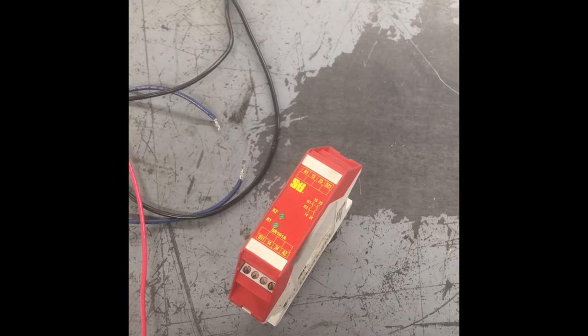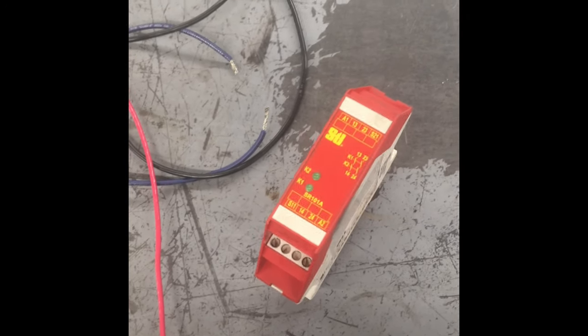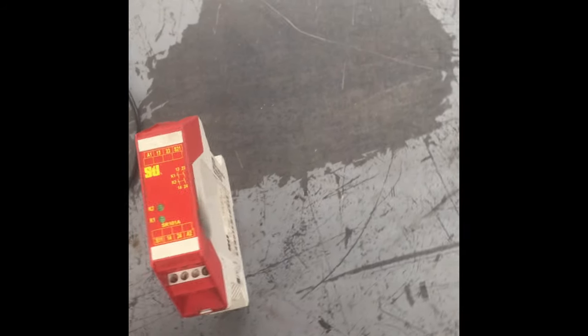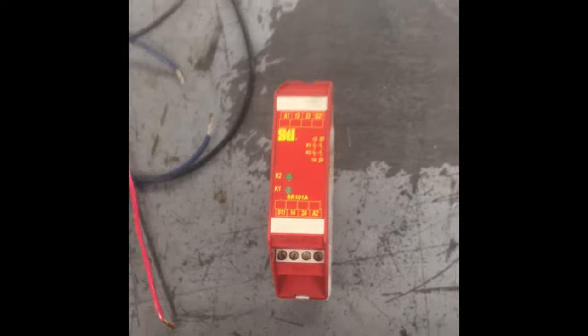Concepts are simple - I went to school for electronics. Anyway, getting down to the meat and potatoes: this is to prevent you from beating your head against the wall. This is a safety relay by Omron, the STI SR101A01, which is a 24-volt model. It passes through up to 250 volts. The biggest problem with this relay is there are two schematics - you can find one on their industrial site and another one somewhere else, but this gives you the basics.